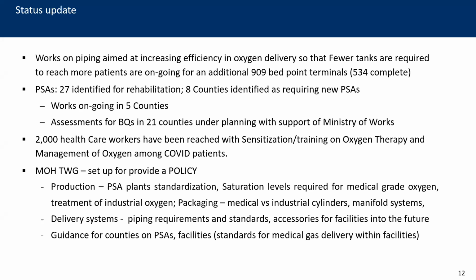We need to standardize PSA plants. They are so unstandardized currently that even just the procurement of spare parts is a challenge. Saturation levels are differing in many ways. The packaging, should it be medical versus industrial cylinders? How should the manifold systems look like? So there's a technical working group that the ministry has set up that is looking at production, is looking at a distribution system, and is going to be putting together standards for medical gas delivery within facilities, so that we have a standard that we can follow moving forward.